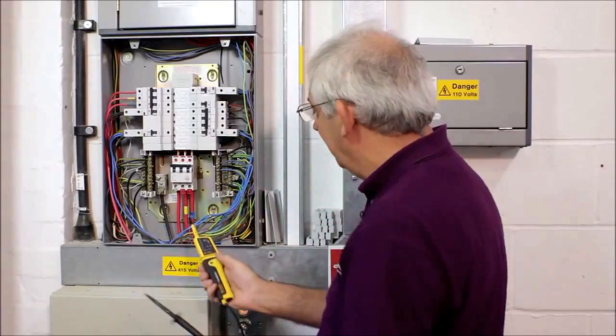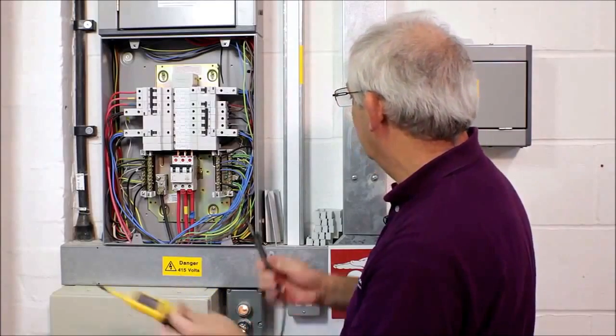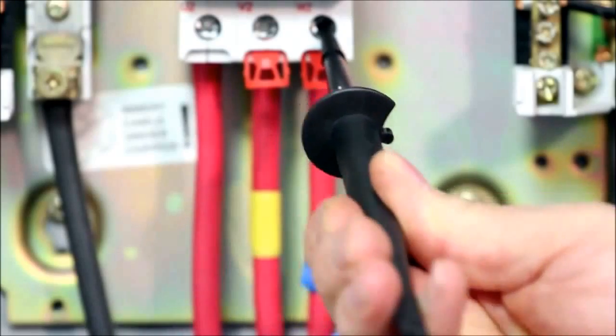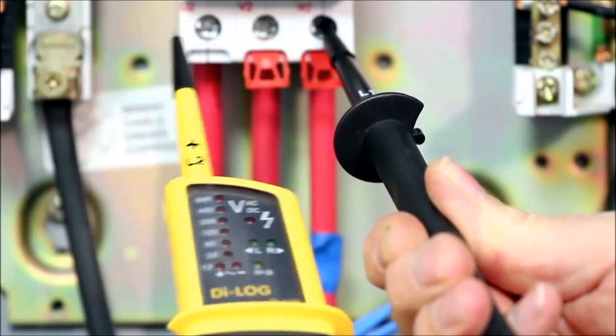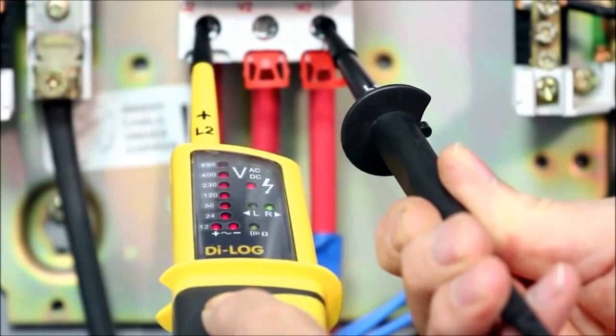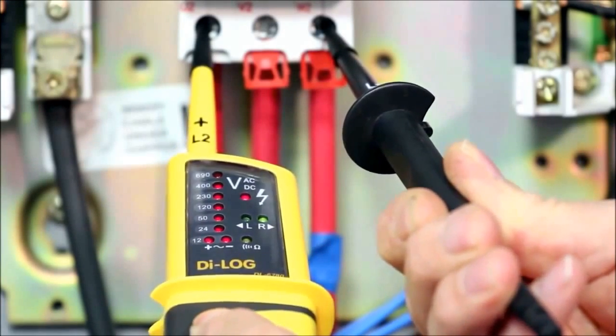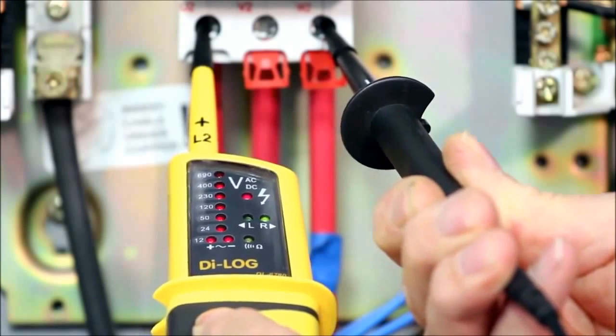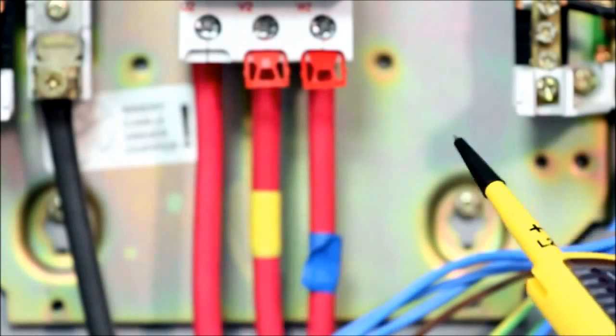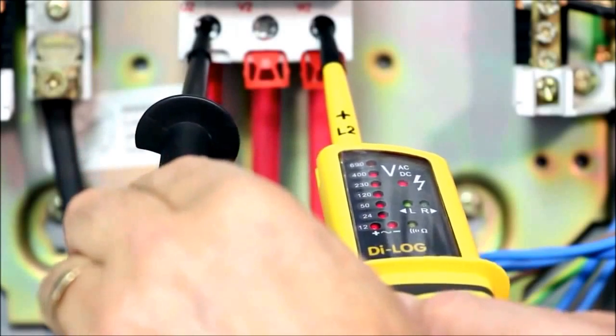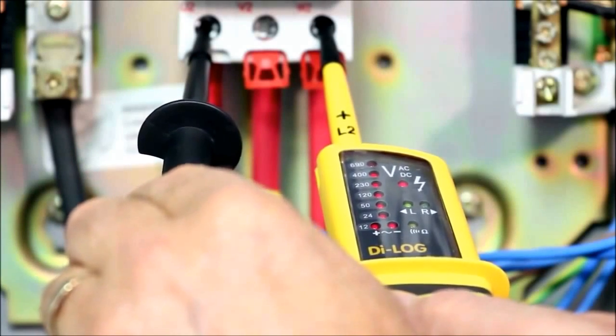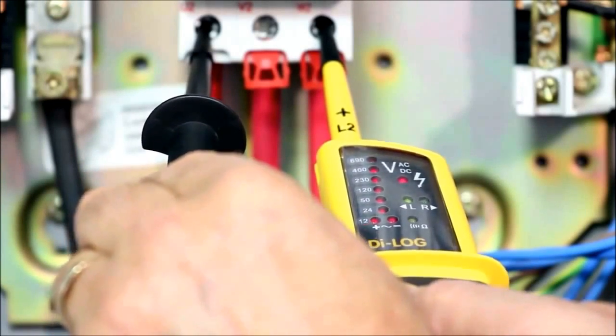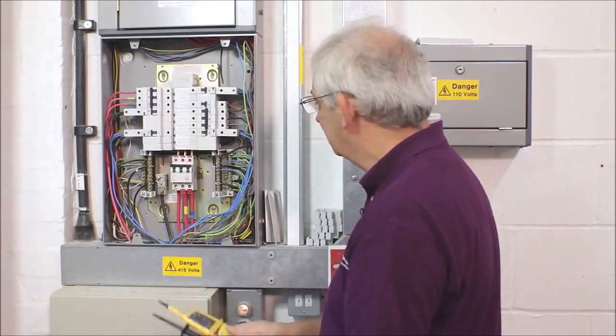and you can see, again, that's telling me that the phase rotation is correct. I then go the other way round, and I need to go L1 goes on L3, and L2 goes on L1, and again you can see it's showing me that the phase rotation is correct. And again, just by way of demonstration, if I get it round the wrong way, and I go L1 onto L1 and L2 onto L3, you can see the left-hand green light lights up, which is telling me the phase rotation is the wrong way. Nice simple method which we can use in any instant.